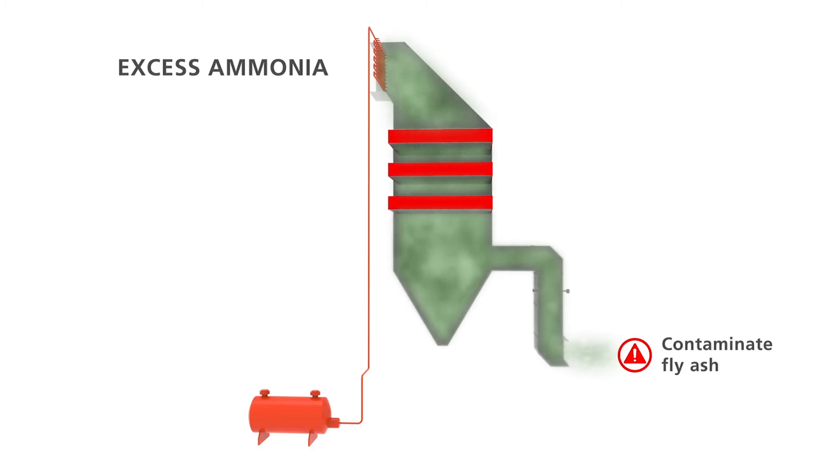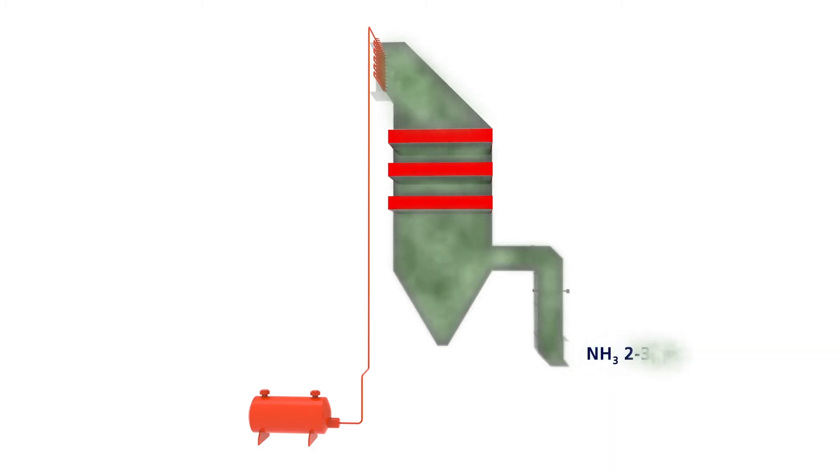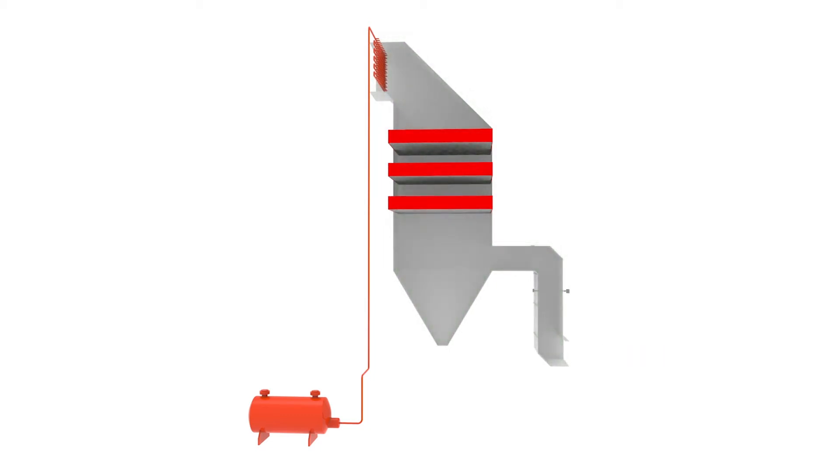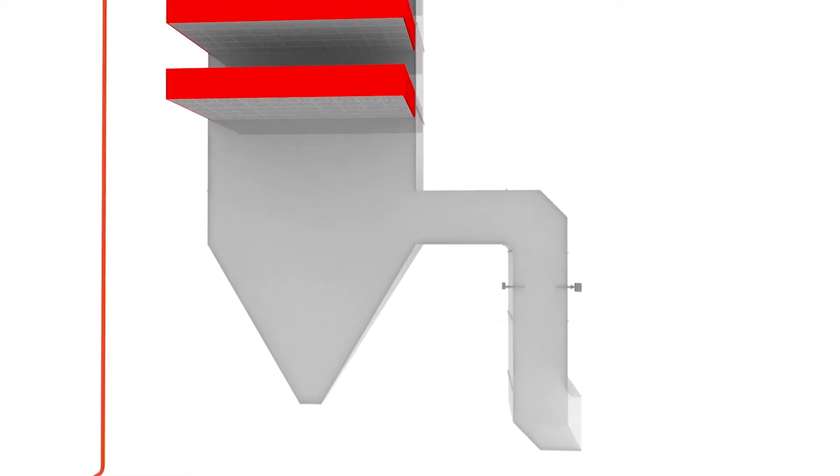So it's important to control the amount of ammonia slip to around 2 to 3 parts per million. Tunable diode laser gas analyzers have taken over from extractive systems as the industry standard for ammonia slip monitoring.